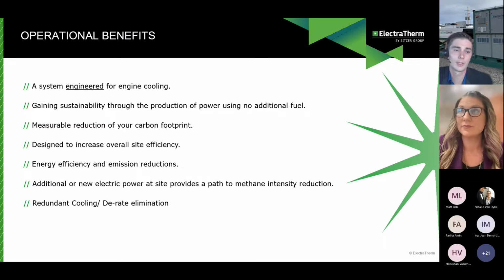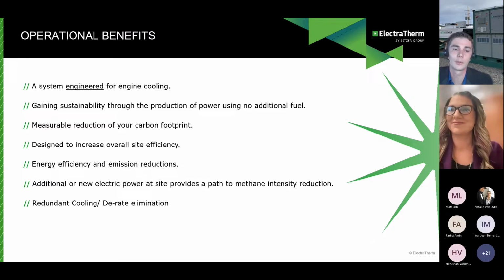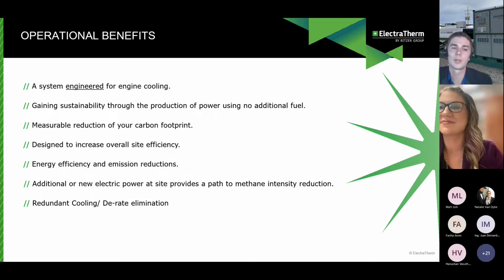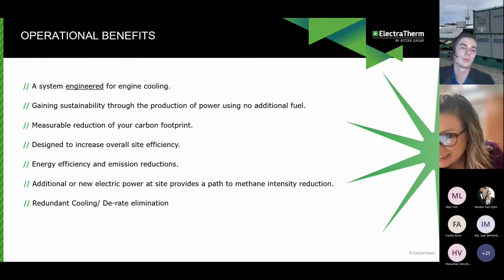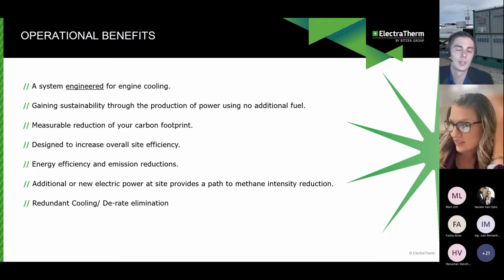And then we provide redundant cooling and derate elimination. We're cooling our refrigerant to a lower temperature than what the engines require, so we're able to cool those engines more significantly. If sites are expecting some summertime derate on the hottest of days, we can contribute to reducing that derate or providing redundant cooling. If a site already has a radiator, maybe that radiator is left as backup, so we would be there for redundancy but also to produce power, and then you'd have that cooler as the backup.